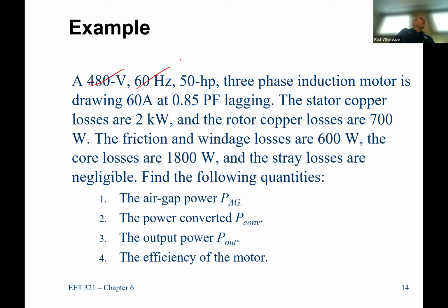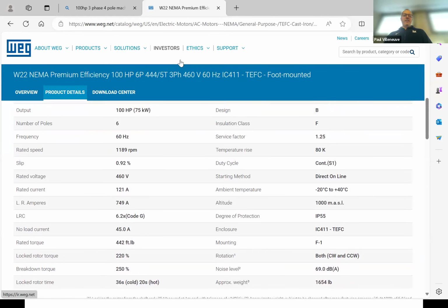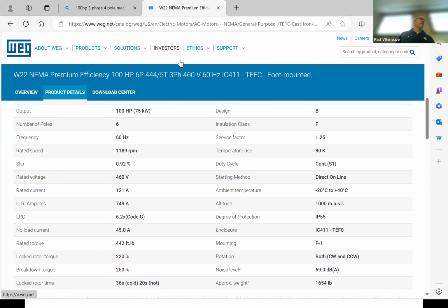The answer is no. That's the nameplate rating of the motor—what it's capable of providing. Does that mean it's actually providing 50 horsepower? No. Most of the time, what's the likelihood a motor is actually operated at its full nameplate rating? Almost nil.